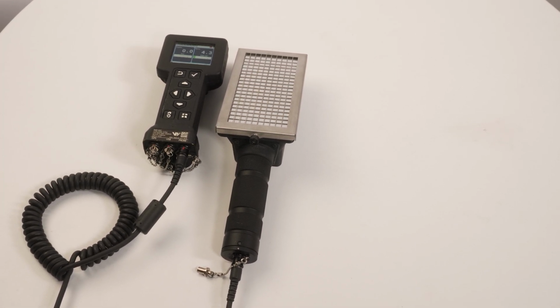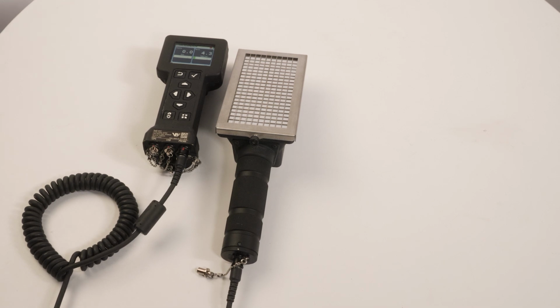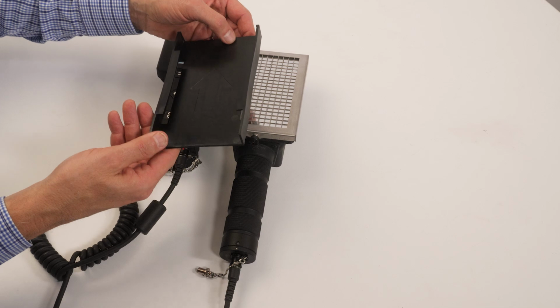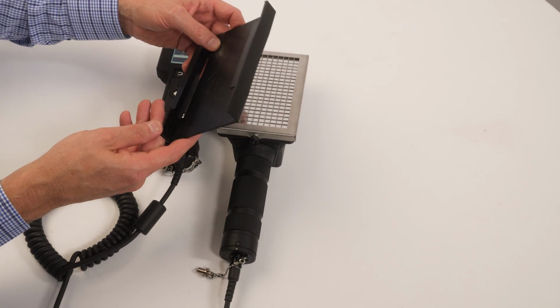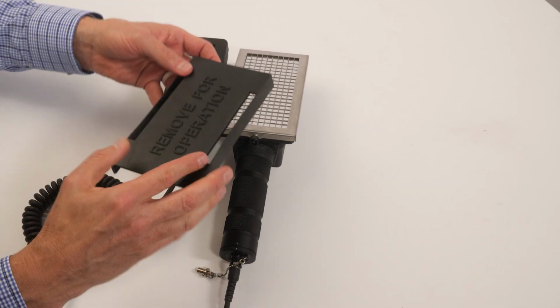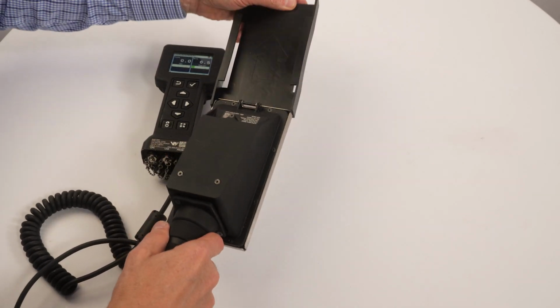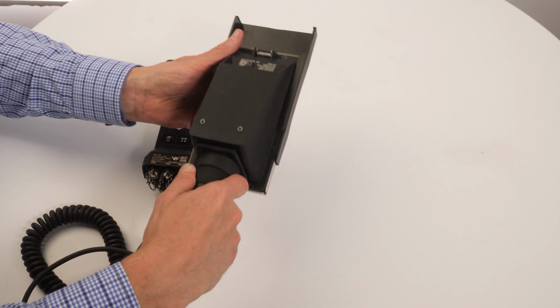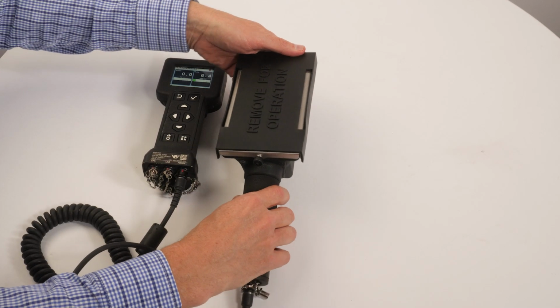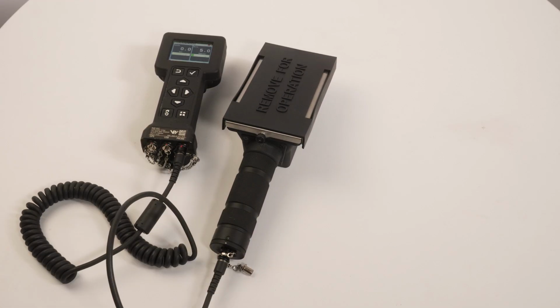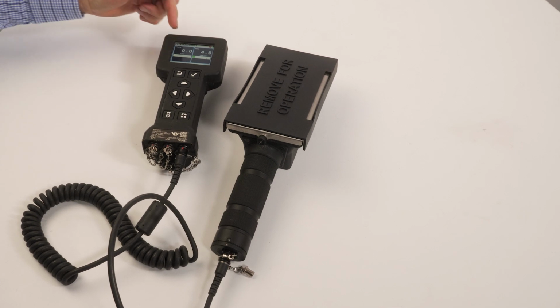and note the readings if they have increased dramatically or not. If you see increased count rates for alpha or beta channel, verify that the increased count rates are due to a light leak by covering the face of the probe with the probe cover or another opaque material such as cardboard, a jacket, or a piece of paper. Leave it in place for 5 minutes, then observe the readings.